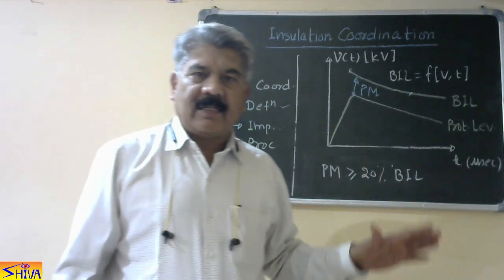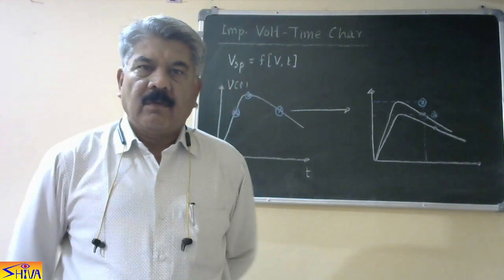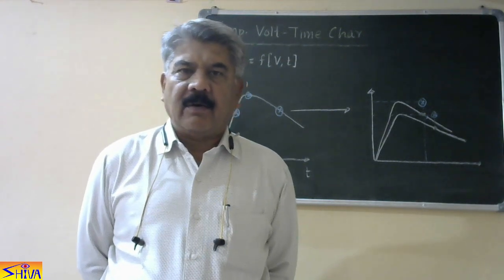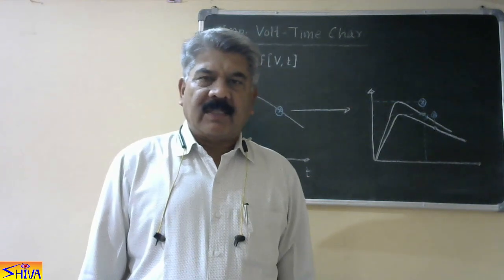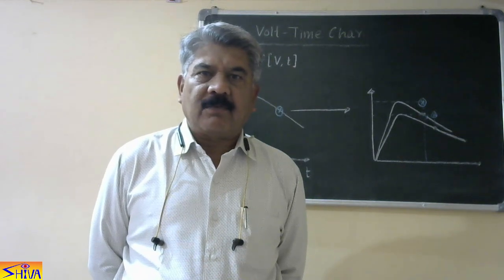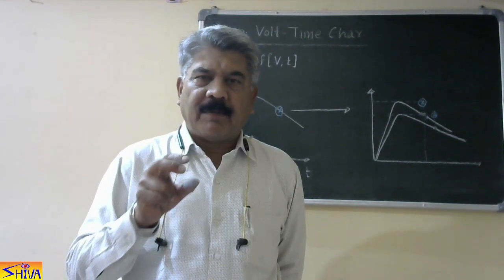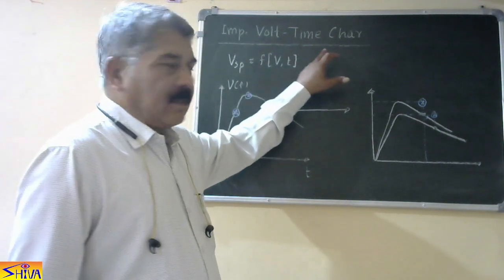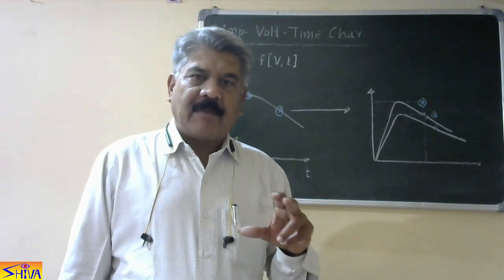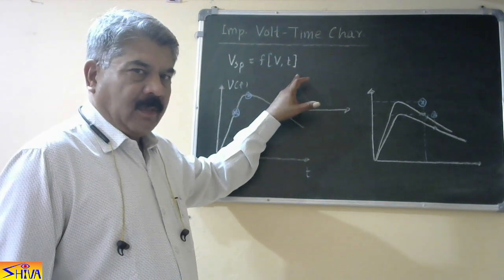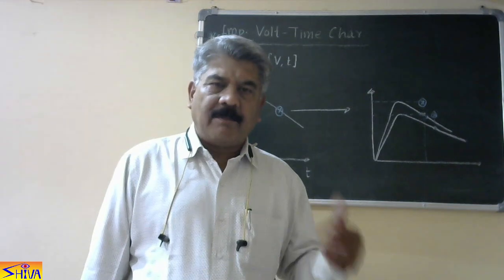Now let us see how the impulse volt-time characteristic is constructed. The impulse volt-time characteristic is the characteristic of spark over voltage versus time obtained with a standard 1.2 by 50 microsecond impulse voltage wave. A series of standard 1.2 by 50 microsecond waves are applied on the insulation and the spark over point is noted. The spark over voltage depends on the voltage as well as the time of application, so we express it as a function of voltage and time. When we apply a standard impulse voltage wave of high amplitude, there are three possibilities.